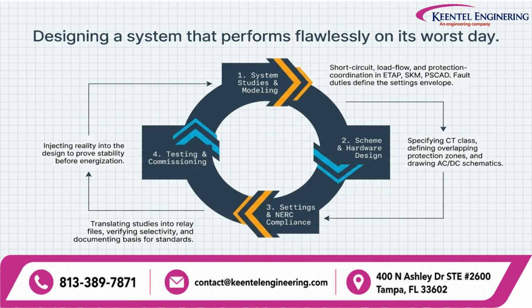Short circuit studies, load flow studies, and protection coordination studies establish the expected operating conditions and fault duties. Tools such as ETAP, SKM, and PSCAD can be used as part of this engineering process. The second stage is scheme and hardware design. This includes specifying CT classes, defining overlapping protection zones, and developing the AC and DC control schematics.